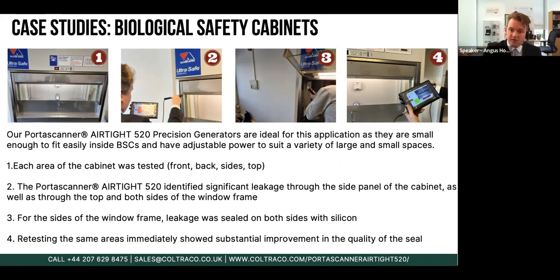But then, as you can see in image 3, just about, we actually sealed this up, or at least we sealed up 2 of the leak sites that we found using some silicon sealant, and went back and retested. And you can see the difference between image 2 and image 4. Where on image 2 we have the red bar, which indicates a leak has been detected and it's very full. Whereas in image 4, the bar is still green and much lower, which showed that we've immediately improved the quality of the seal. And we can be confident now that area at least is as airtight as it needs to be.